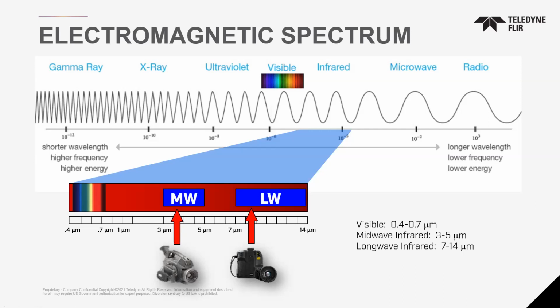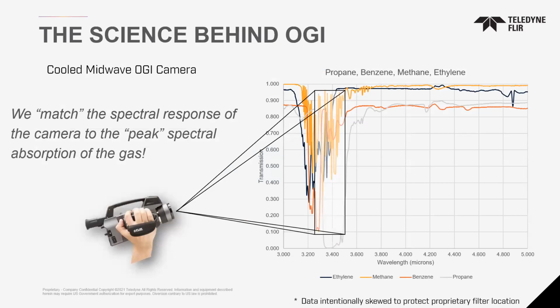I promise there's not a test after this, and we're not going to dig too much more into the theories of how these cameras work, but just to let you know a little bit of the basics here. So what we do is we actually match the spectral response of the camera to the peak spectral absorption of the gas. Like I said, only some of these wavelengths are going to come back to the camera because that gas is going to impede it. So where the gas absorbs all of that reflected light, that's where we're going to match our cameras or our lenses to that gas.